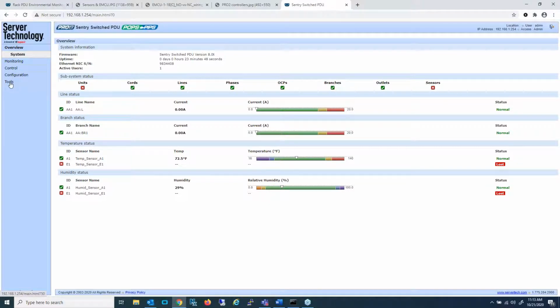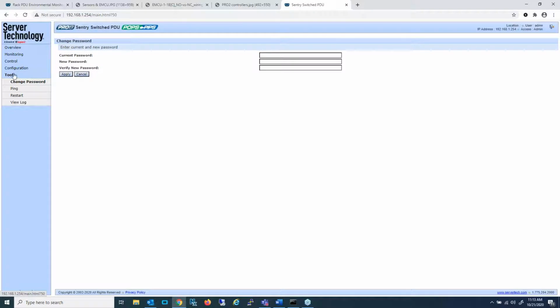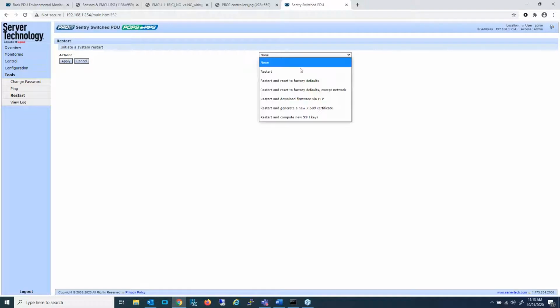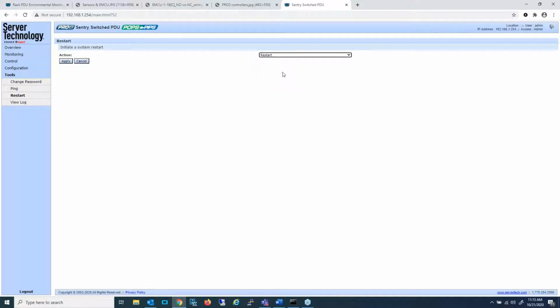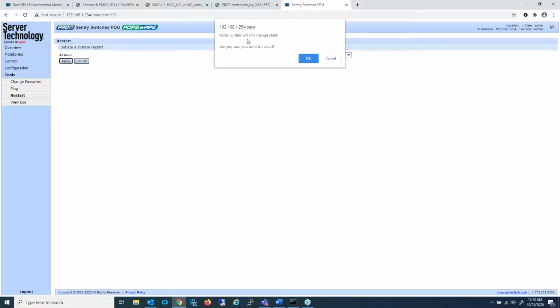So what do you have to do? In order to clear that, you either have to attach or reattach the device, or you have to go to the tools option on the left, go to restart, and do a simple standard restart, which, if it is a switched PDU, as it is in this case, you will note that the outlets will not change state. A restart does not affect the status of the outlets.